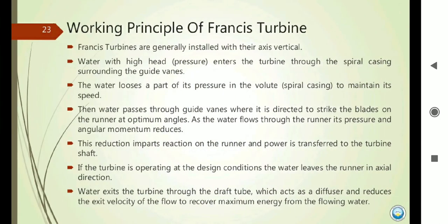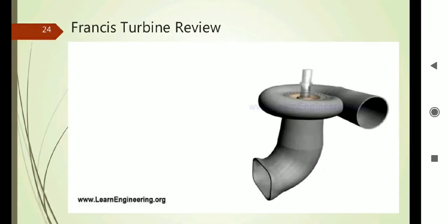Regarding the working of the Francis Turbine: it is generally installed with a vertical shaft and water pressure enters the turbine through the spiral casing. Water loses part of its pressure in the volute. At the entry of the turbine the pressure is maximum and at the exit it is minimum. After passing through the guide vanes, water is directed to the blades of the runner at the optimal angle. As water flows through the runner, its pressure and angular momentum reduce. This reduction causes the reaction of the runner, and power is transmitted to the turbine shaft. Water leaves the turbine in the axial direction.